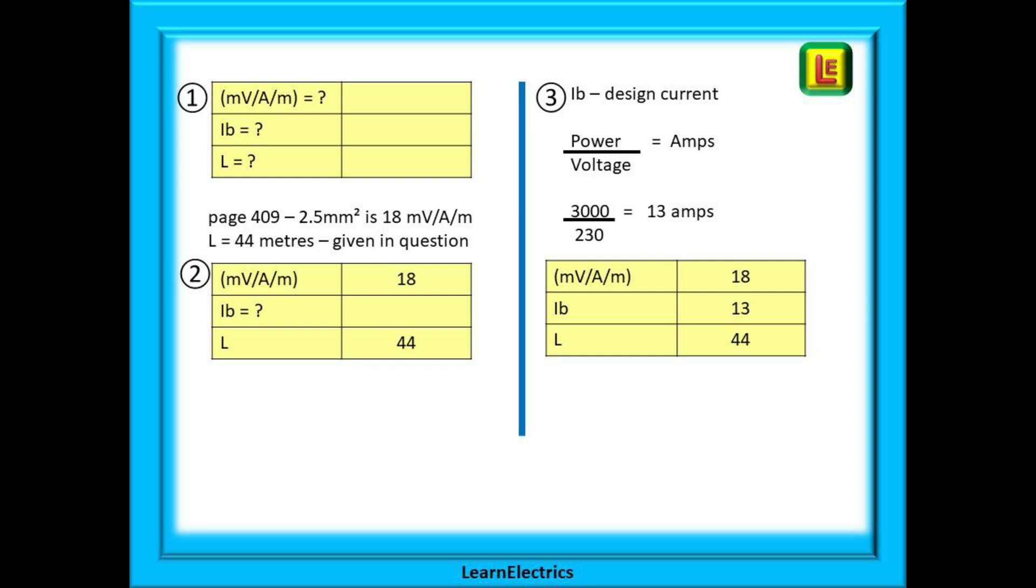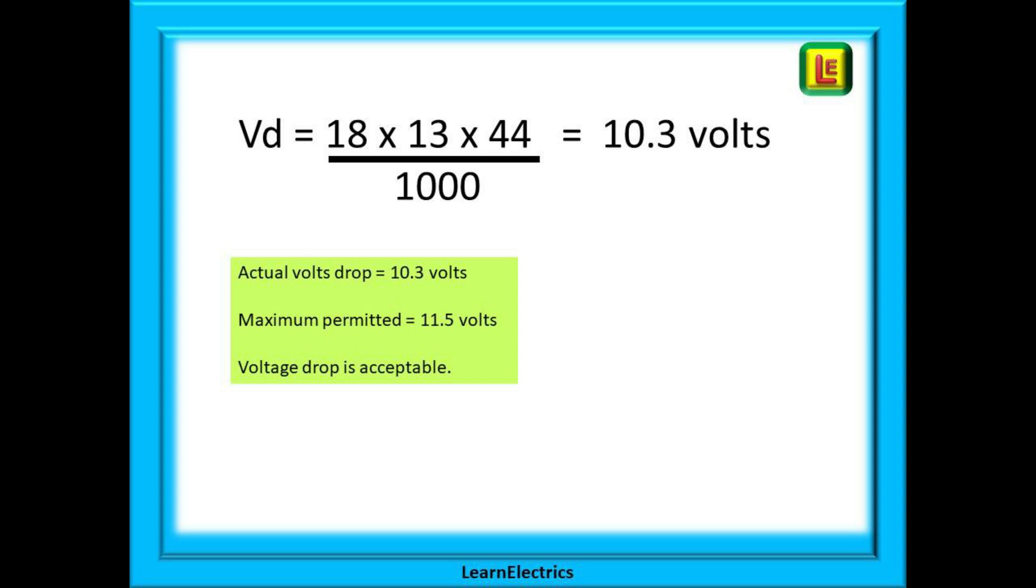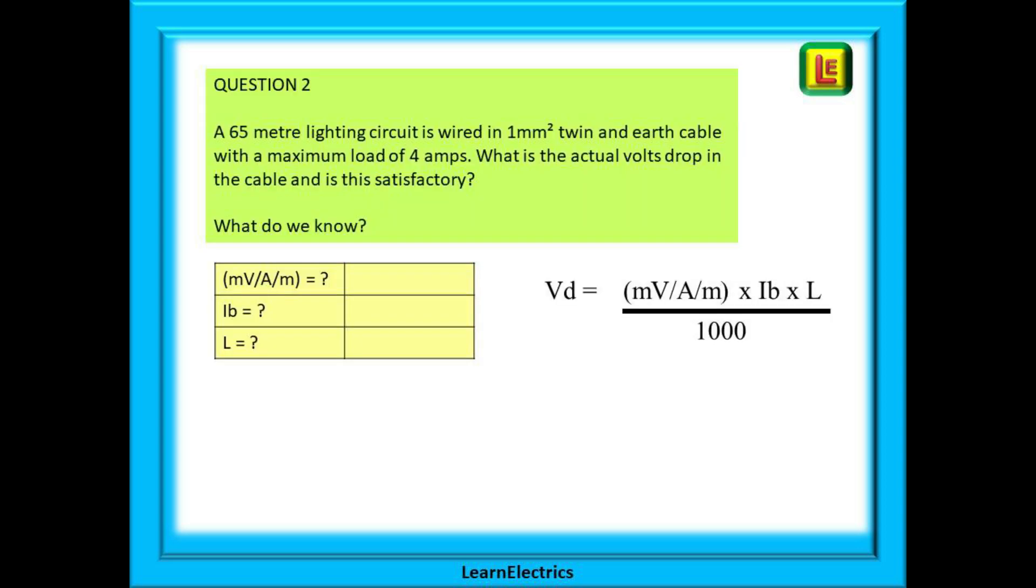3 kilowatts is the same as 3000 watts, so 3000 watts divided by 230 volts gives us 13 amps of current. We can enter this in the information box and move on to calculating the actual volts drop. The voltage drop will be 18 multiplied by 13 multiplied by 44 and divided by 1000, and the answer that pops out of the calculator should be 10.3 volts, give or take a very tiny amount. So our actual volts drop is 10.3 volts and the maximum permitted is 11.5 volts. Our actual volts drop is within the limits and it is acceptable. How easy is that?